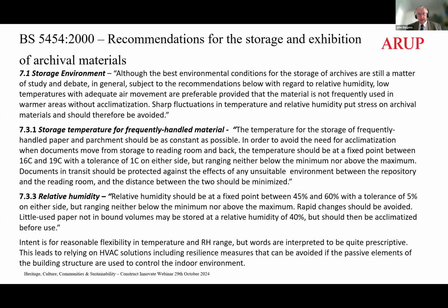The main thing is to avoid sharp fluctuations in temperature and humidity. The thing most likely to cause sharp changes is the operation of the HVAC systems themselves. So one has to be careful about over-designing and picking equipment sized for peak winter or summer conditions or peak internal loads, when most of the time that never eventuates.